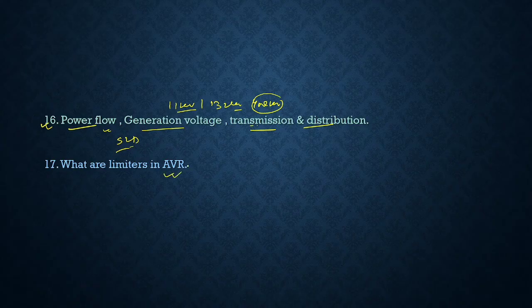What are limiters in AVR, automatic voltage regulator. Again they started asking questions related to the generator. We use automatic voltage regulation to provide excitation supply to the generator, so there are limiters: under excitation limiter and over excitation limiter. Generators have to work within the capability curve. You can also go through the capability curve. They can ask, if you cross these limits, then your rotor and stator winding will be heated up. So within this range, AVR has to work. For that reason, you cannot over excite, and also you cannot under excite the generators. So you have to be within this limit of UEL and OEL, over excitation limit. You can describe all these things to interviewers.